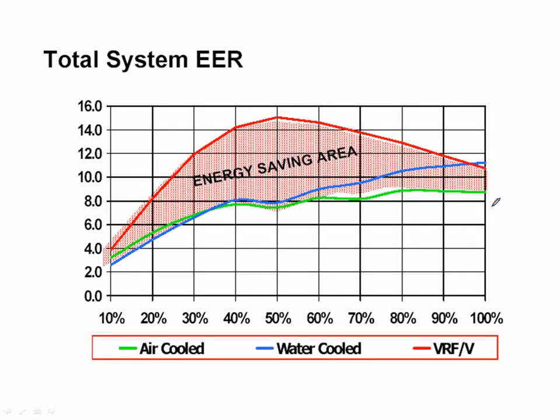Obviously, that's the case. My company, we do air-cooled chillers, water-cooled chillers, and VRF, so we're trying to be a little more agnostic. Every once in a while, even on their chart, it shows the water-cooled winning. Just to be clear, the reason you'll see this on some of the VRF guys' literature and language is that they're taking this green line and this blue line. Those are at the 90.1 minimum conditions for those type of chillers.